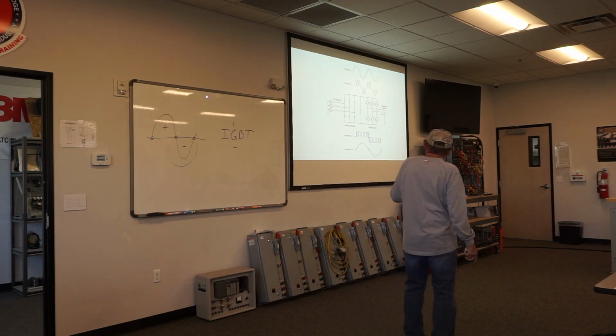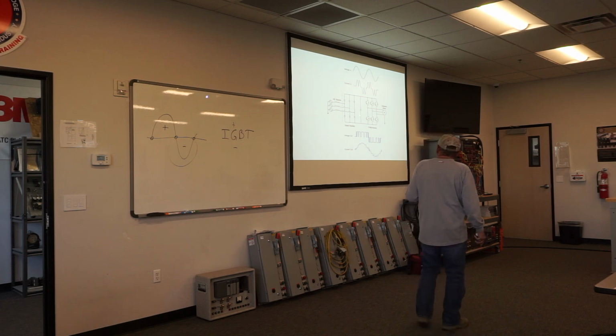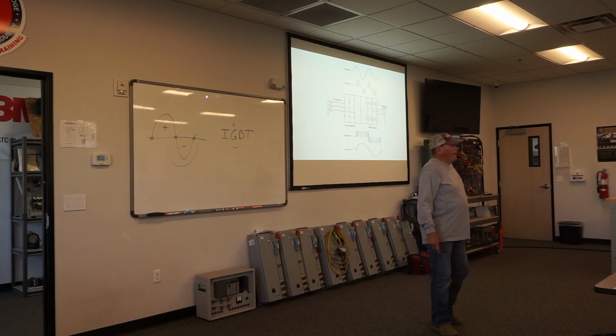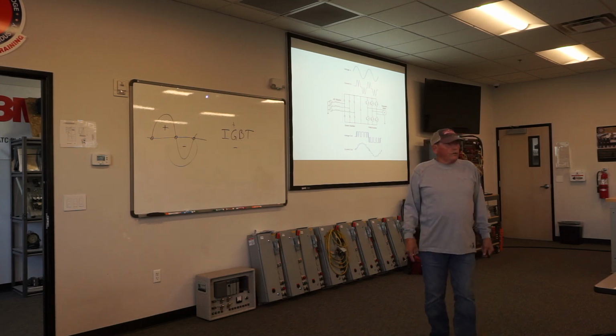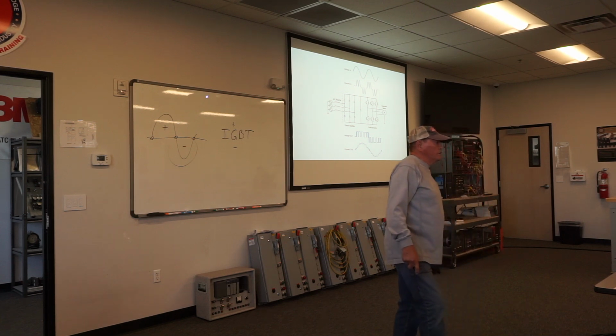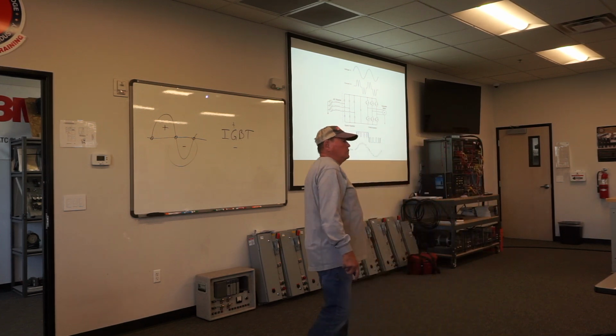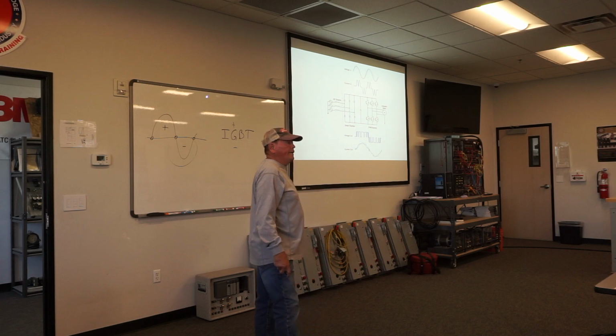So there's the basic function of a variable speed drive. Now remember, this DC bus has to be somewhere around 600 plus volts. How do we get 600 volts off a 480 volt signal? Huh? Anybody remember? How does 480 volts put out 600 volts?